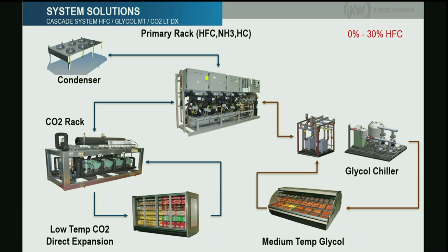So again, the charge is reduced, but you still have HFCs in your system. And now you have HFC, glycol, and CO2 in the store. And the technicians, you guys need to be proficient managing all of this, right? So the system gets complicated even though we reduce the refrigerant charge. So that is what we were seeing in many cases.